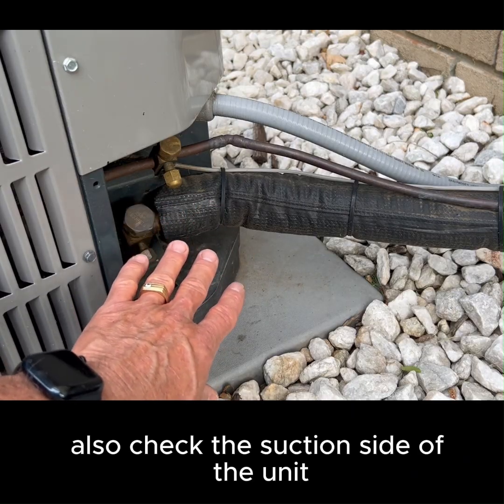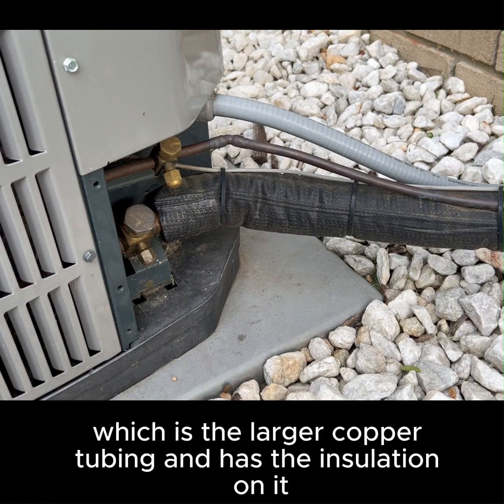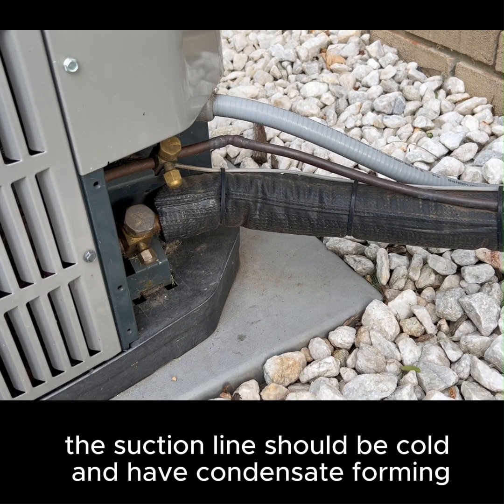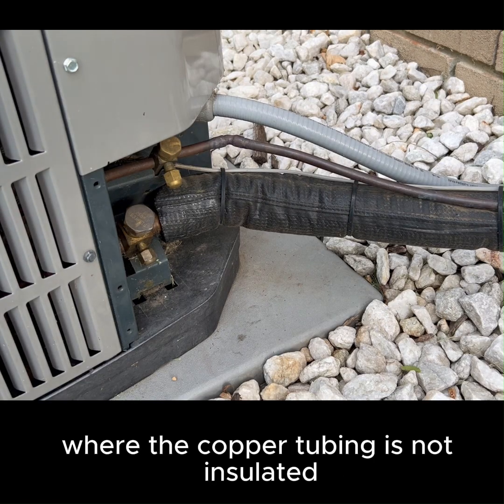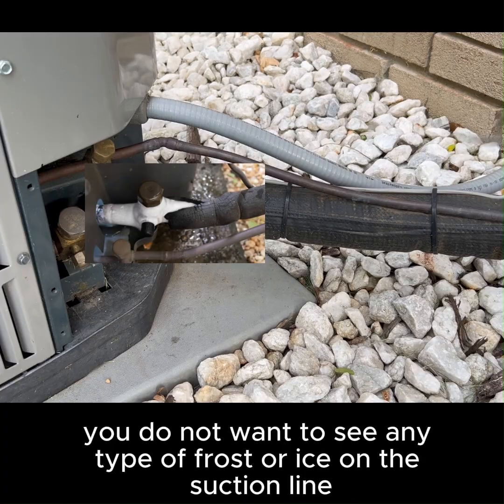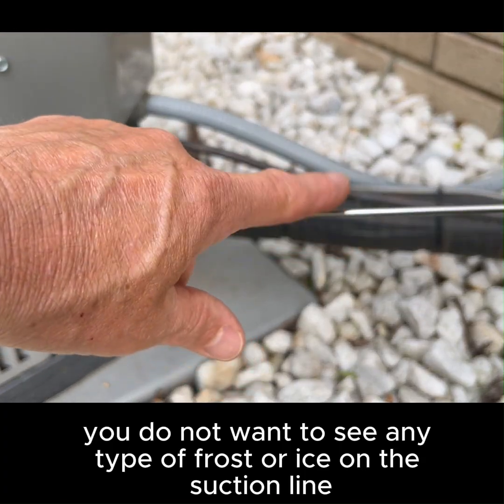Also check the suction side of the unit, which is the larger copper tubing and has the insulation on it. The suction line should be cold and have condensate forming where the copper tubing is not insulated. And once again, you do not want to see any type of frost or ice on the suction line.